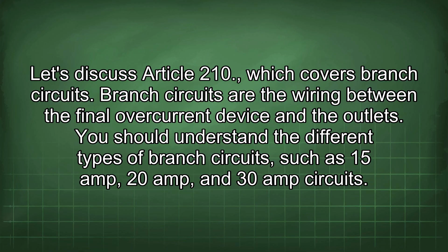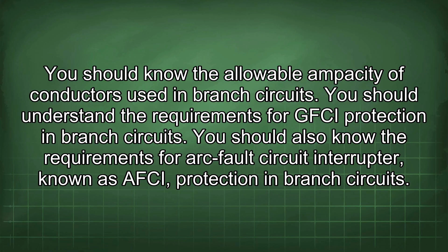Let's discuss Article 210, which covers branch circuits. Branch circuits are the wiring between the final overcurrent device and the outlets. You should understand the different types of branch circuits, such as 15 amp, 20 amp, and 30 amp circuits. You should know the allowable ampacity of conductors used in branch circuits. You should understand the requirements for GFCI protection in branch circuits. You should also know the requirements for arc fault circuit interrupter, known as AFCI, protection in branch circuits.